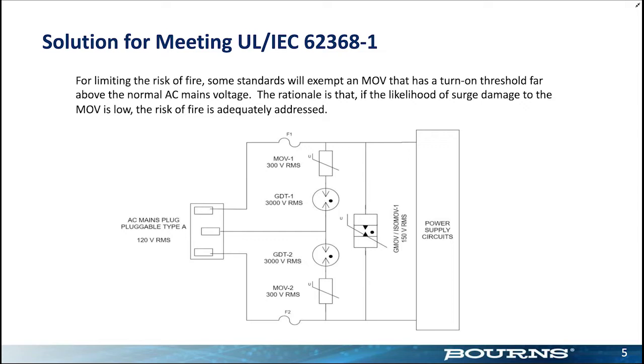But if you can put that clamping voltage very high, even though there's a voltage across the device, the leakage becomes very, very small. One way to do that is to put a GDT in series, and you can see that on the circuit diagram here. I have an AC line voltage, and I show 2 GDTs in series with 2 MOVs, and that has been around for a long time. That's a very common configuration that's been around for decades before my time.